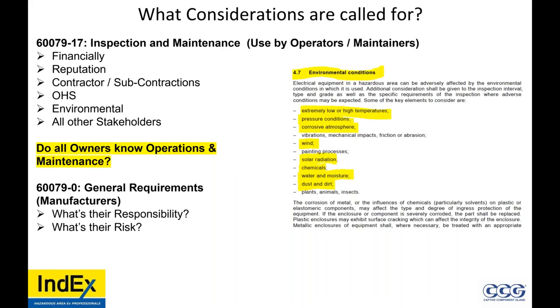What considerations are called for when it comes to ingress protection and other environmental conditions? Well, according to 60079-17, inspection and maintenance, which is used by operator maintainers, environmental conditions such as high temperature, low temperature, pressure conditions, corrosive environments, vibrations, wind, solar radiation, chemicals, water, moisture, dust, and dirt. Okay. That's for the owners and operators, which ingress protection is barely even mentioned in their standards. Well, what about for the requirements for manufacturers? 60079-0. What's their responsibility? What's their risk?